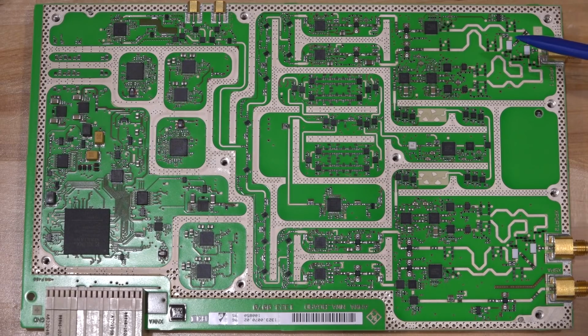So let's take the signal going into the instrument. We come over here after the couplers, we have two paths. On one path, we have a digital attenuator. On the other path, we go straight in, and you can see some black diodes over here, 3 of them in series, and these are probably for clamping. And if you look carefully, you can see that there's some tricks played on the transmission lines in order to absorb the capacitance of those lines and create a uniform attenuation across frequency. This is a common technique as well.